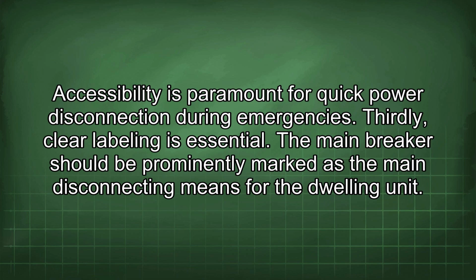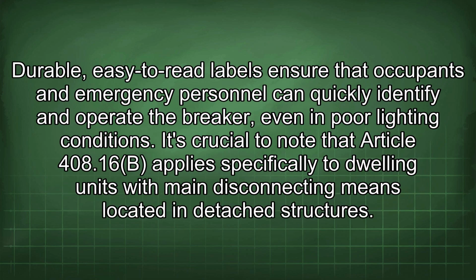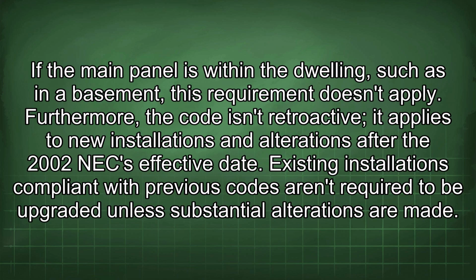Thirdly, clear labeling is essential. The main breaker should be prominently marked as the main disconnecting means for the dwelling unit. Durable, easy-to-read labels ensure that occupants and emergency personnel can quickly identify and operate the breaker, even in poor lighting conditions. It's crucial to note that Article 408.16(B) applies specifically to dwelling units with main disconnecting means located in detached structures. If the main panel is within the dwelling, such as in a basement, this requirement doesn't apply.